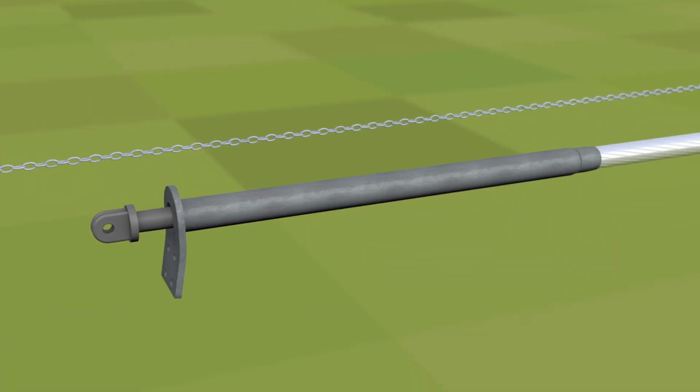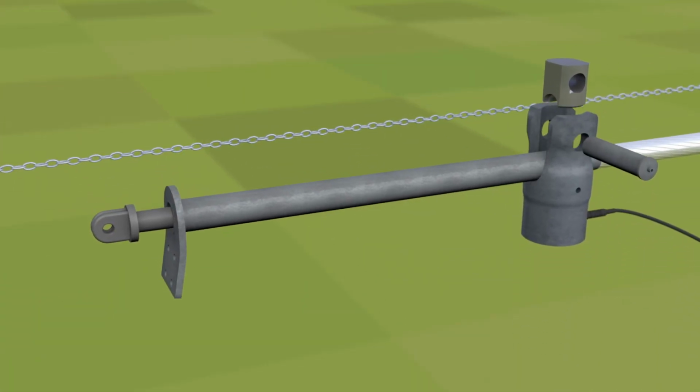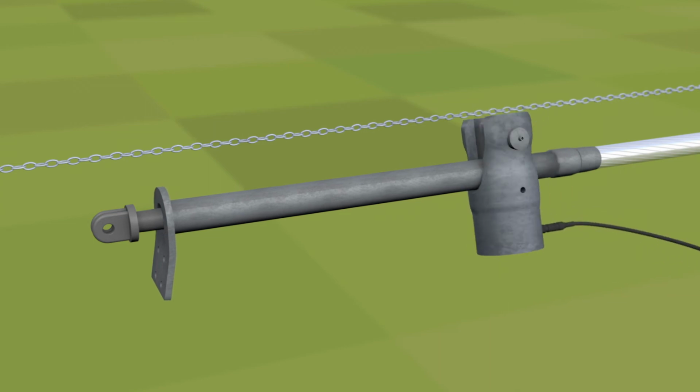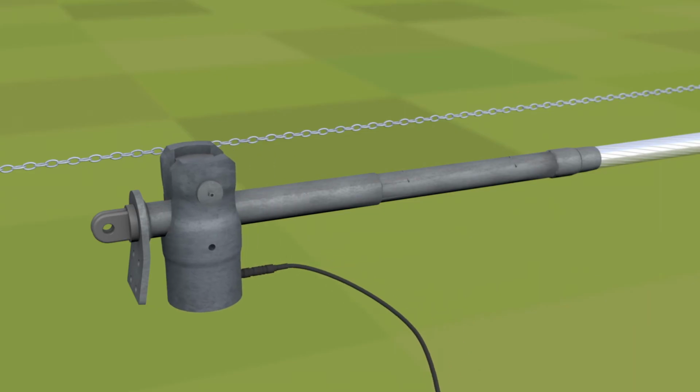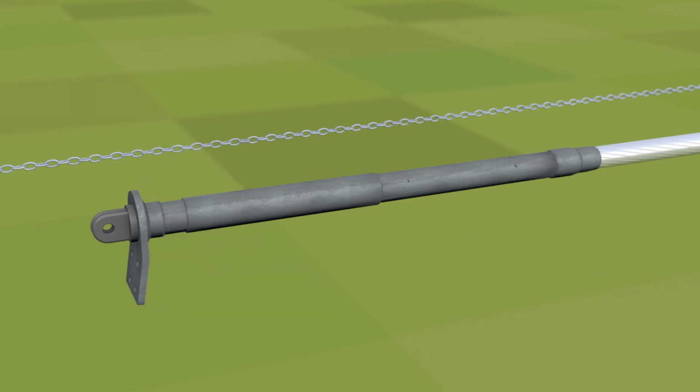Next, the aluminium sleeves are pressed on the conductor. Pressing occurs from the conductor end towards the eye. The head should be rotated every few presses, just as you would with ACSR. When the pressing is finished, we file off the flashing to make sure the surface is smooth.